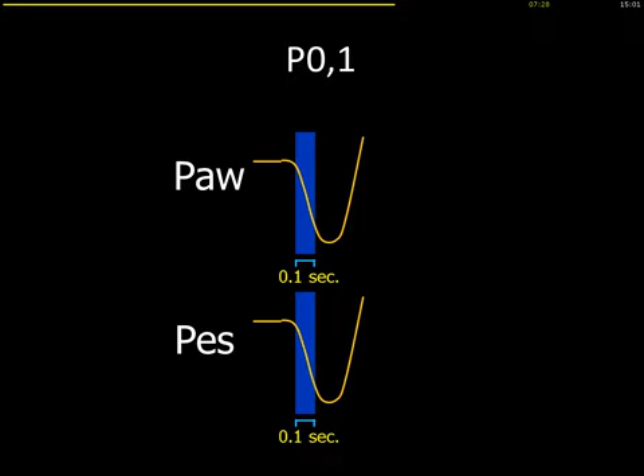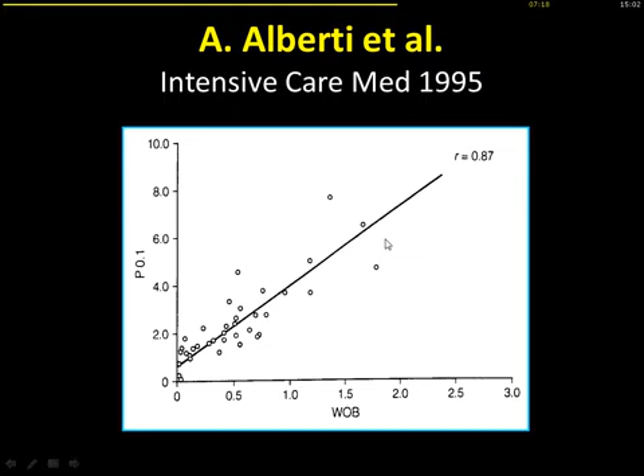The patient pulls from the ventilator against an occluded valve, and he does not know that the valve is closed. So he puts the force and the speed he thinks is necessary for his next breath. After 200 or 250 milliseconds, he realizes that the valve is really occluded, and then he will react. But during the first 100 milliseconds, he does not know. So if we measure the drop in pressure during the first 100 milliseconds, we can pretty well estimate the work of breathing.